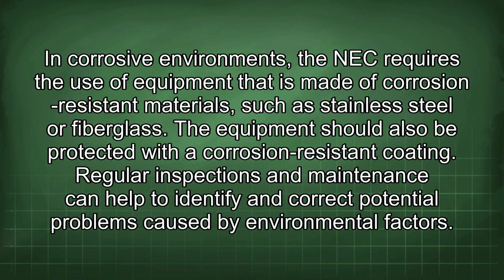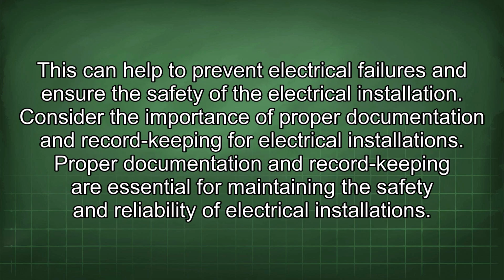In corrosive environments, the NEC requires the use of equipment that is made of corrosion-resistant materials, such as stainless steel or fiberglass. The equipment should also be protected with a corrosion-resistant coating. Regular inspections and maintenance can help to identify and correct potential problems caused by environmental factors. This can help to prevent electrical failures and ensure the safety of the electrical installation.